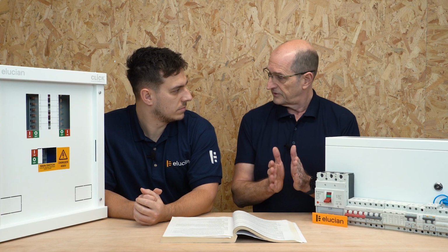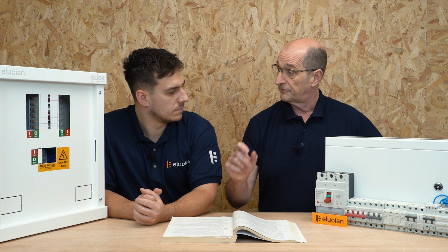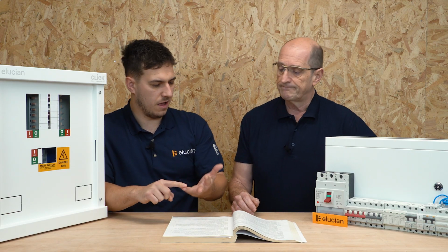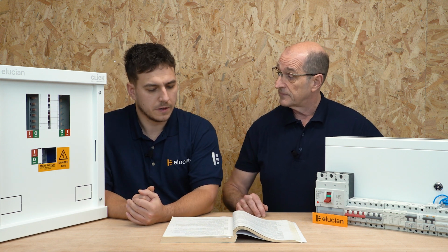And so in indent 4 of 531.3.3, it deals with residual sinusoidal alternating currents of up to 1 kilohertz. So suddenly we've got something that's normally 50 hertz, Type A AC, and then this thing goes, actually I can have a range of frequencies and this device will continue to function as it should, even when the frequency range is much wider. And again, this is more tied to frequency controlled motors and the like. Most motors nowadays where you want speed control are going to go for a Type B device arrangement. So even things like air source heat pumps are going to be included in there. PV could be. Battery storage, those types of... EV may well be in there. All of that would be where you would think about a Type B device.